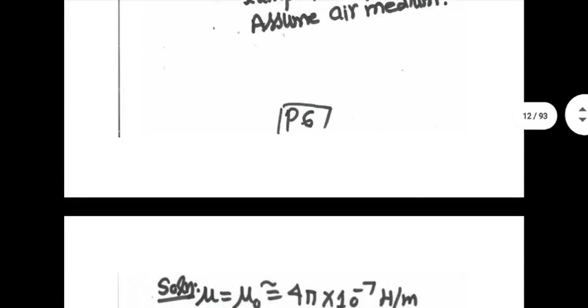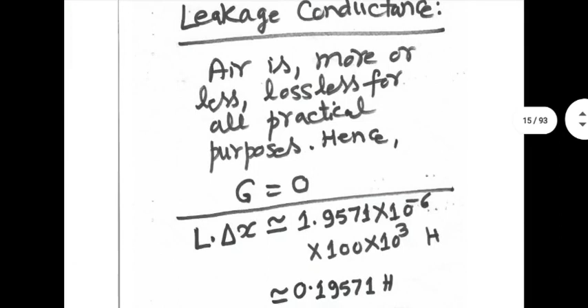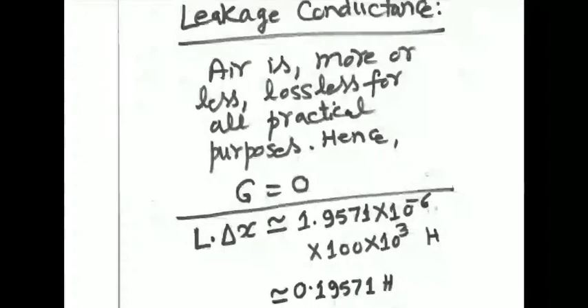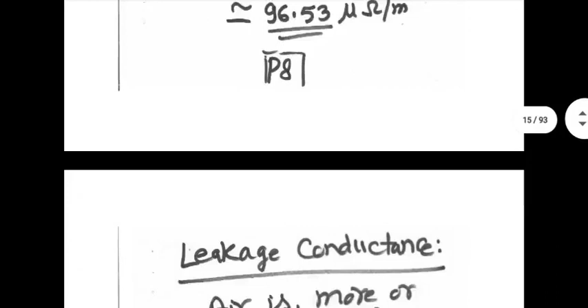Good. So once you have calculated these 4 values, in fact, one of them is 0 anyway in this case, now you do this multiplication. L delta X, I'm calling it X, it could have been delta Z also. The value of L that we have calculated is 1.9571 microhenry per meter. 1.9571 into 10 to the power minus 6 multiplied by length in meters, 100 kilometer into 10 to the power 3. So this works out to 0.19571 Henry approximately. Not very small. The reactance will be 2 pi FL. You can do the calculation. It works out to be 61.48 ohm approximately.